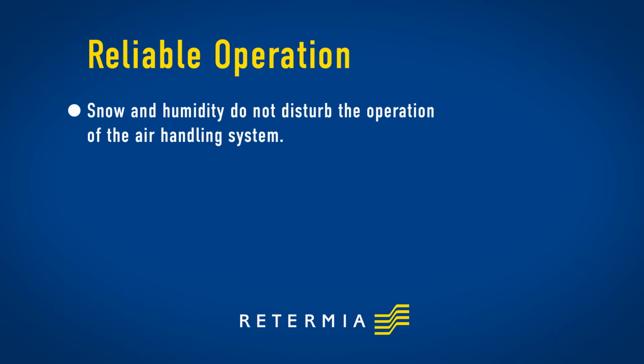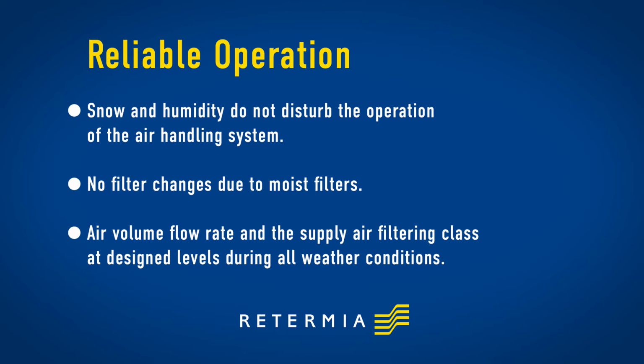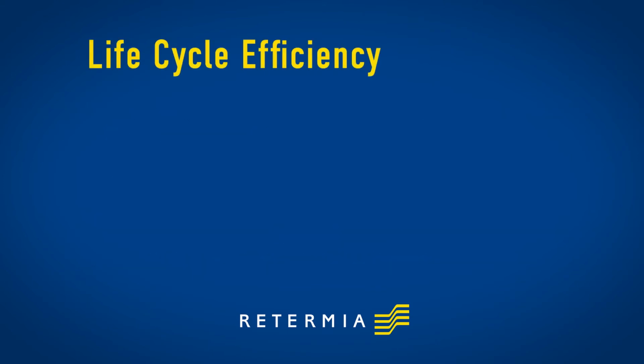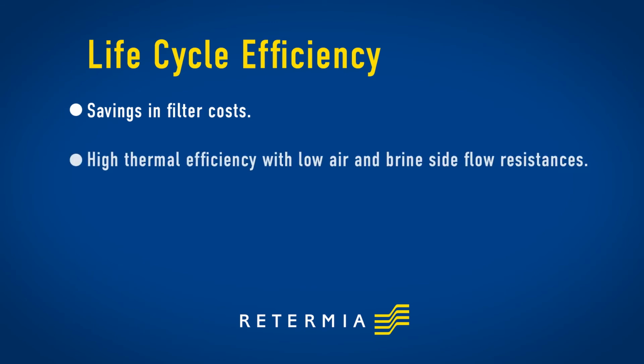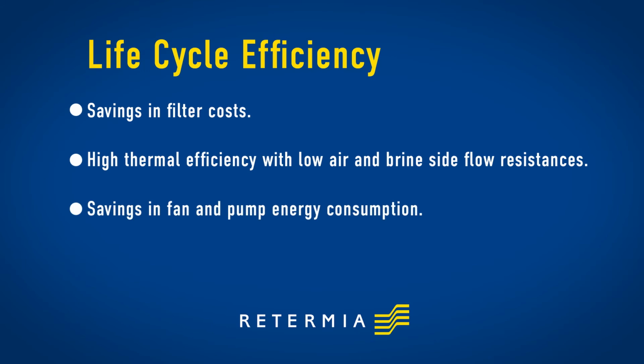Snow and humidity do not disturb the operation of the air handling system. Additional filter changes due to moist filters are avoided. Air volume flow rate and supply air filtering class remain at design levels during all weather conditions. The Retermia system brings savings in filter costs. With needle heat exchangers, high thermal efficiency is achieved with low air and brine side flow resistances. Fan and pump energy consumption is lower than in a conventional heat recovery solution.